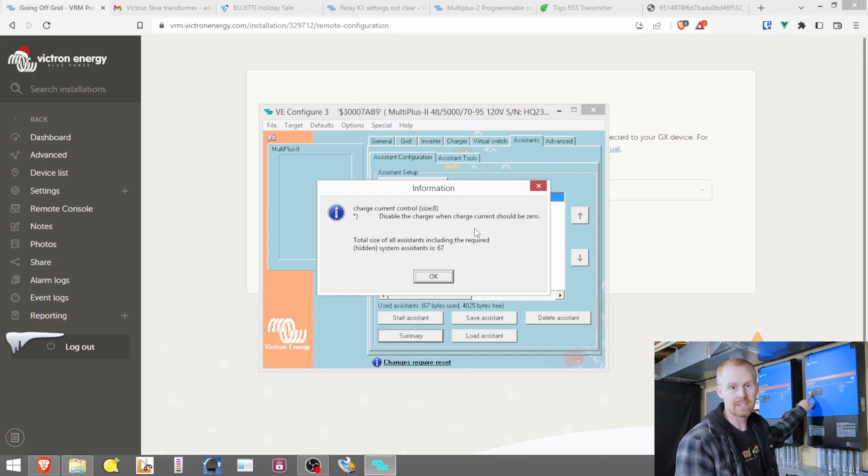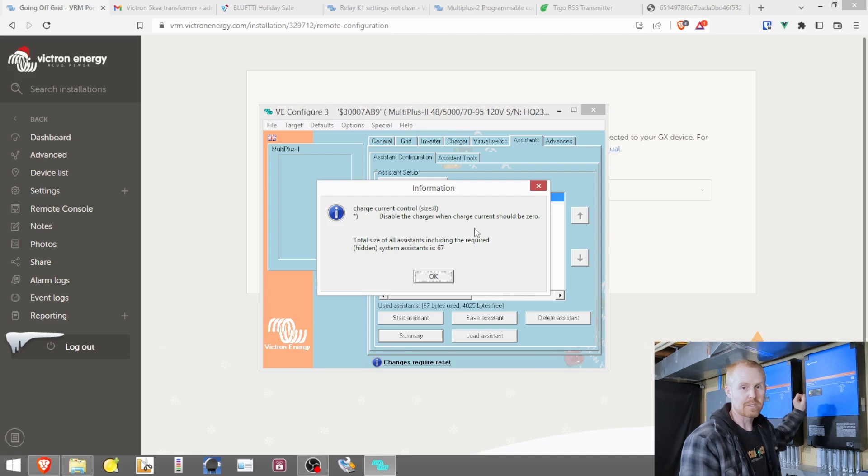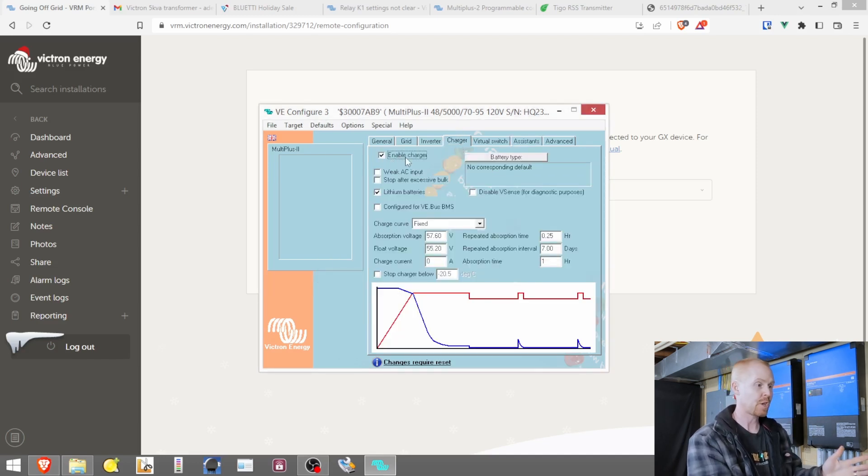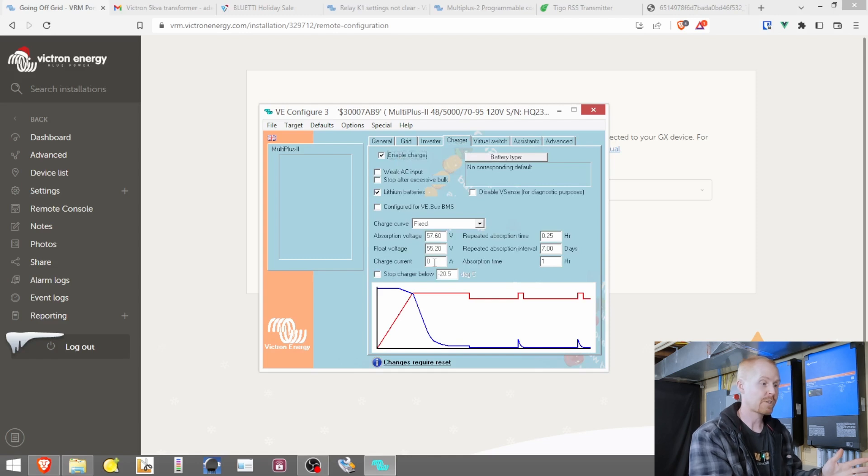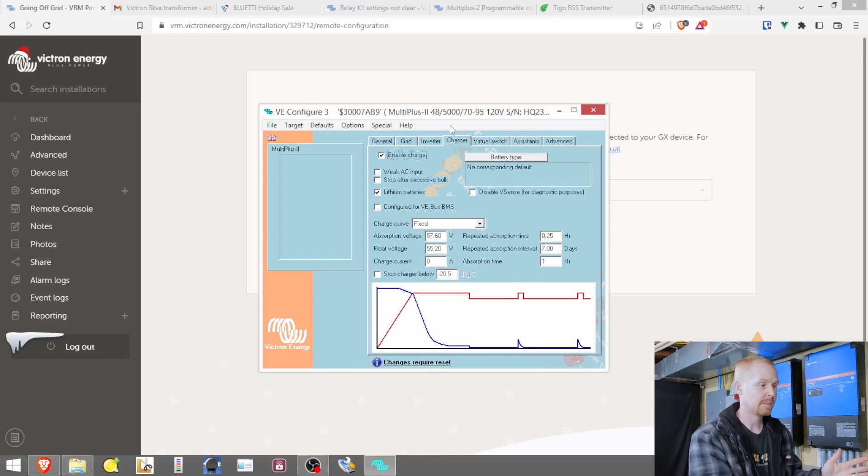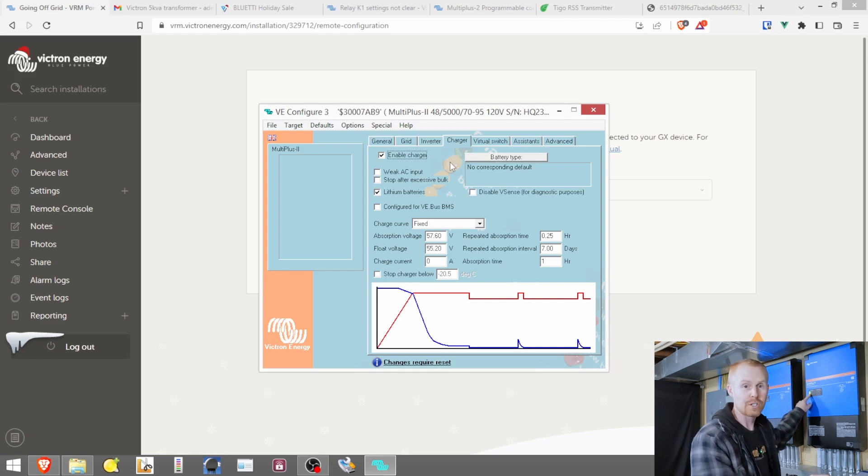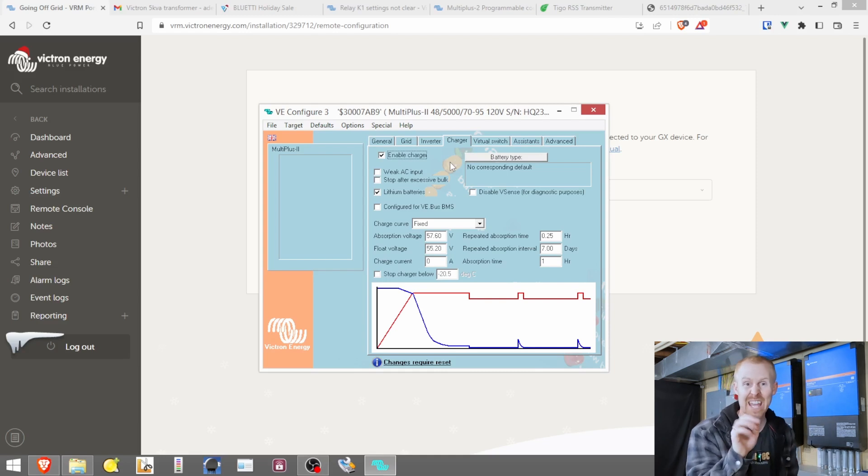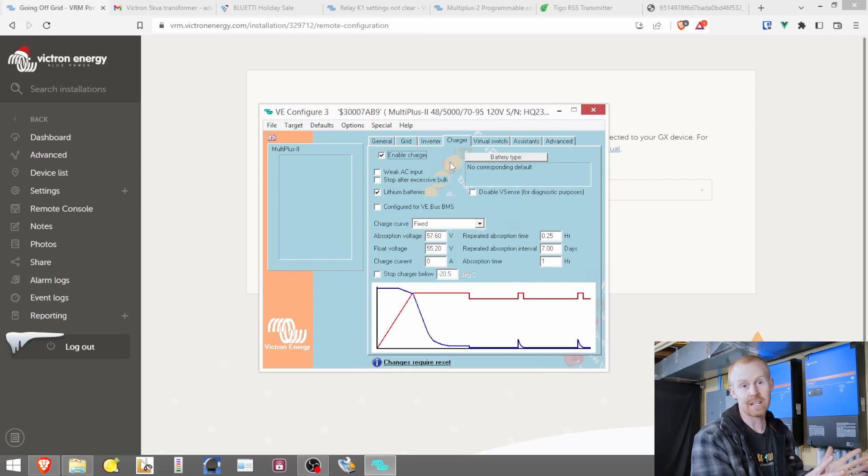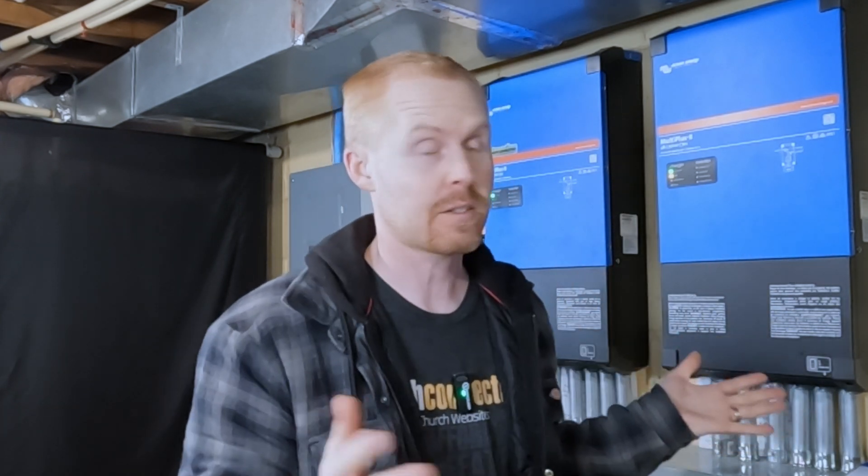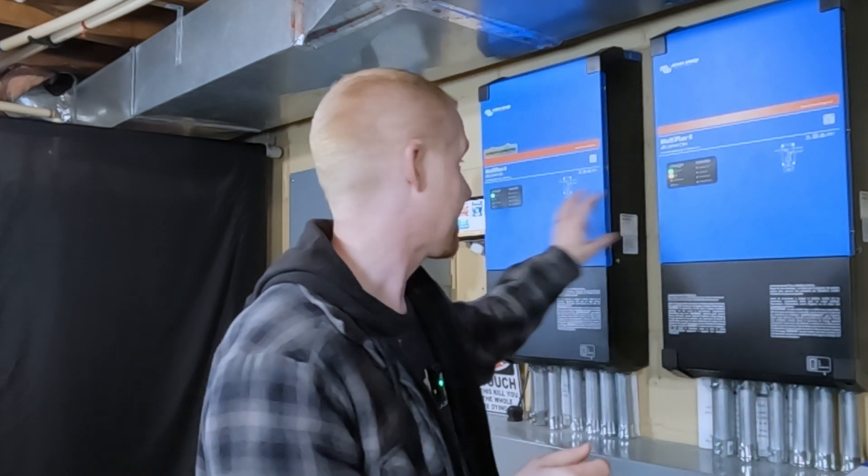That's why this light stays on. Because if we look at this charger in here, charger is enabled. Even though the charge current is set to zero. So it's trying to charge with nothing or with half an amp, and it's not supposed to. When I turn on the relay on the Cerbo telling the system to charge from the grid, that still works. That still kicks both of these up. It still charges with 20 amps for both inverters. But when it's supposed to be zero, it's not disabling the charger. All because I didn't add the assistant here.